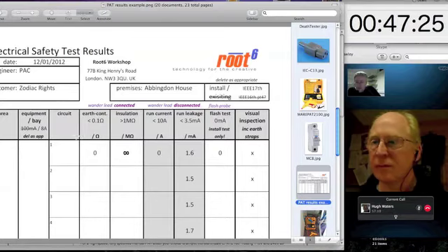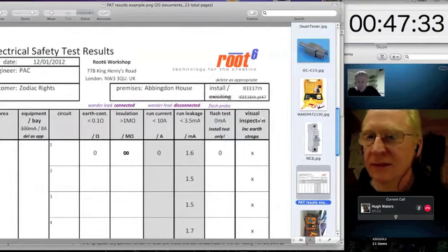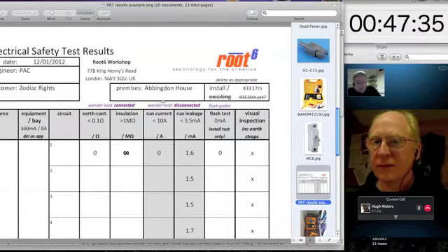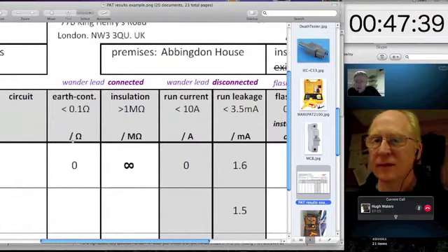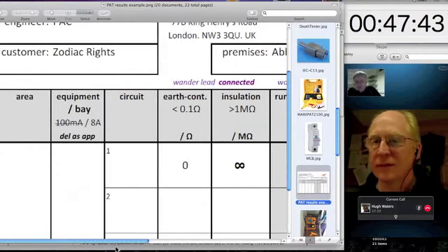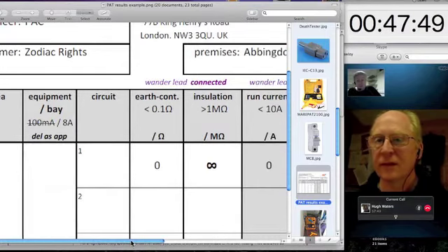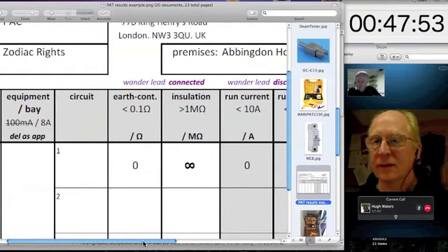So we've got our various tests across the top here: earth continuity, an insulation test, a run current test, a run leakage test, a flash test, and a visual inspection. And then I've got little notes above each of the columns telling the engineer what he should have connected to do that test. And then there are some score outs where you've got options. You might be testing a piece of equipment, in which case you only want to be testing its insulation at about 100 milliamps. You don't want to be testing it with lots of amps.